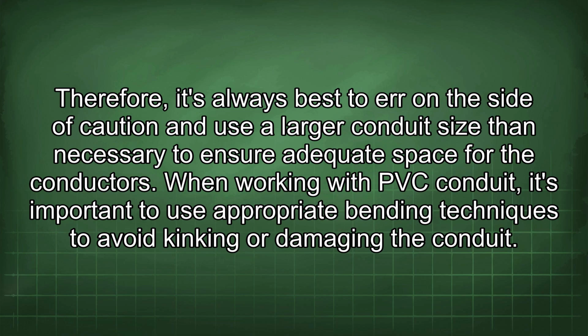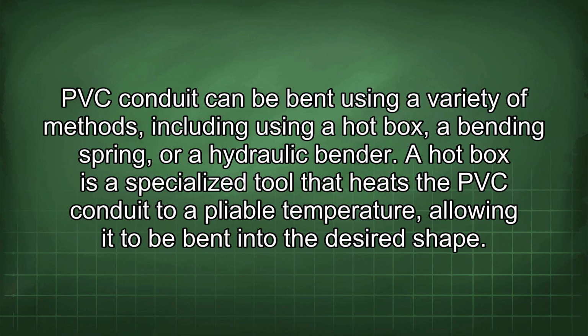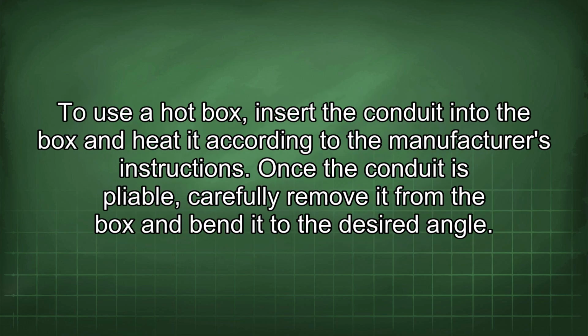When working with PVC conduit, it's important to use appropriate bending techniques to avoid kinking or damaging the conduit. PVC conduit can be bent using a variety of methods, including using a hot box, a bending spring, or a hydraulic bender. A hot box is a specialized tool that heats the PVC conduit to a pliable temperature, allowing it to be bent into the desired shape. To use a hot box, insert the conduit into the box and heat it according to the manufacturer's instructions. Once the conduit is pliable, carefully remove it from the box and bend it to the desired angle.